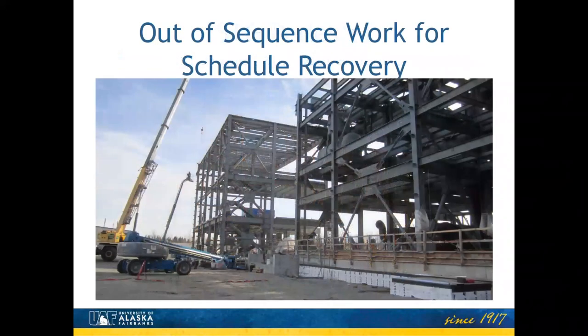And this is showing how we got around some of the late steel deliveries. In the foreground is the baghouse end of the building, and that's the steel we asked the boiler supplier for last, so naturally it arrived first. In the background of that is the steam turbine generator building, and then there's this 115 foot gap in the middle waiting for the steel that supports the boiler. And so we built some things out of sequence that caused a little more work than it otherwise would have, but it kept us closer to our schedule.